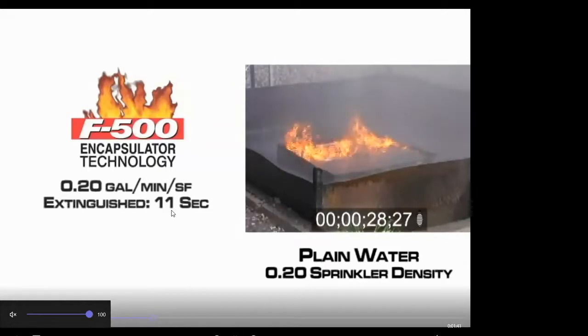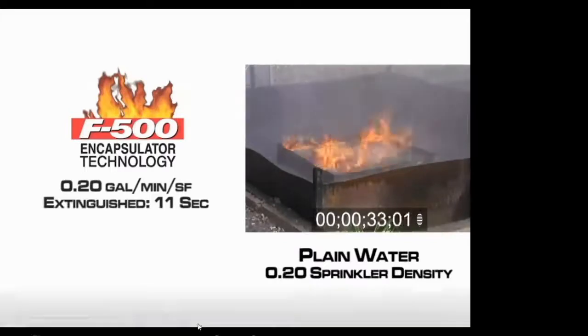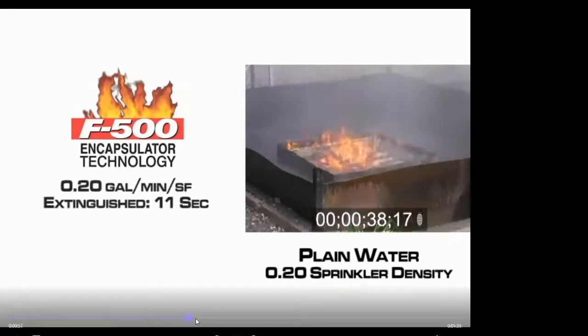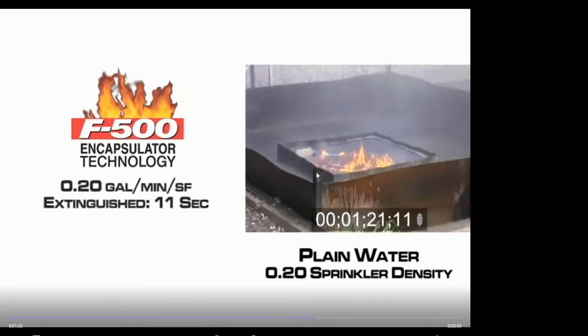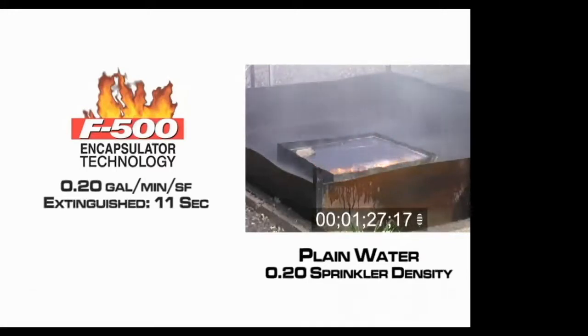So they cut the sprinkler density down, and in 11 seconds we put the fire out, provided burn back resistance, cooled everything down. With the plain water here at 0.2, we've got a little bit of burning around the edge because the water's not cooling the steel. And what do we have in the under turbine lube oil? Tons of steel. So you still have a heat source to keep igniting your fuel. That's one of the main advantages of that heat reduction characteristic.